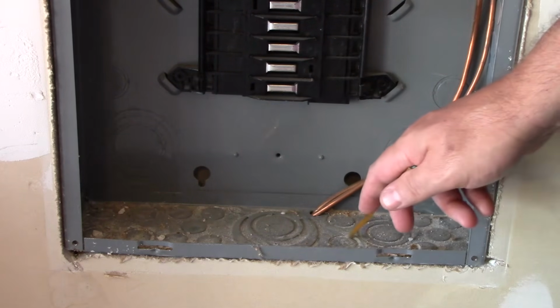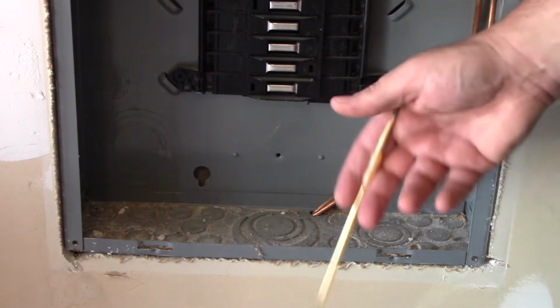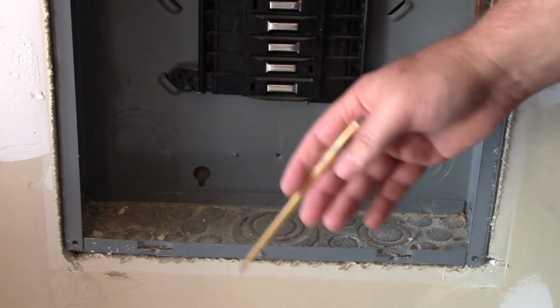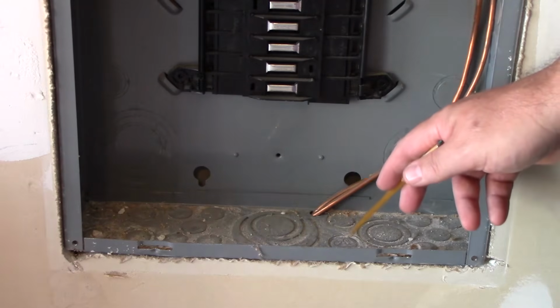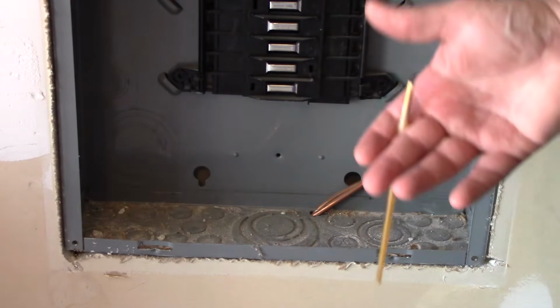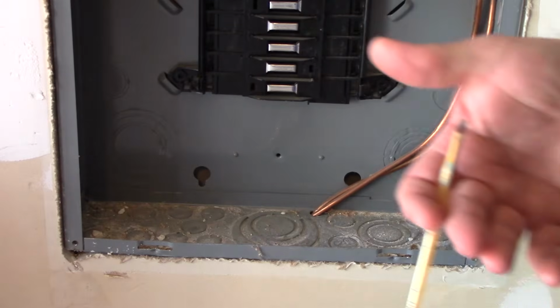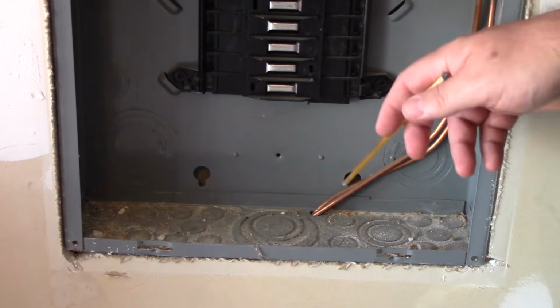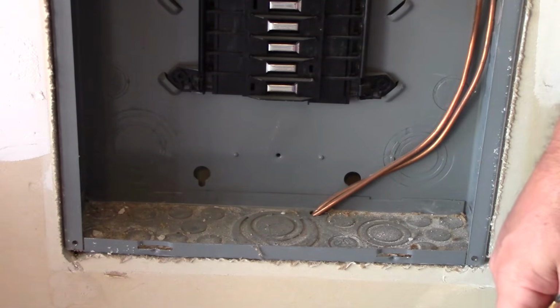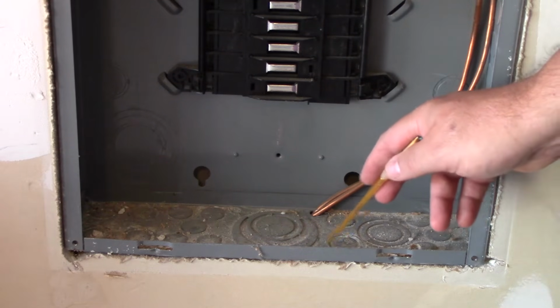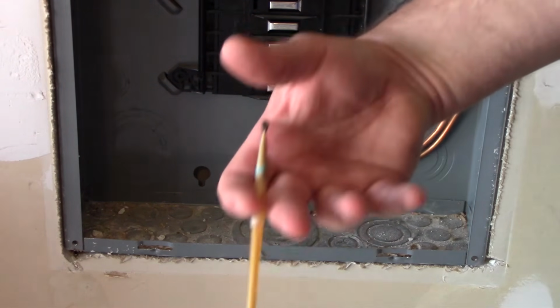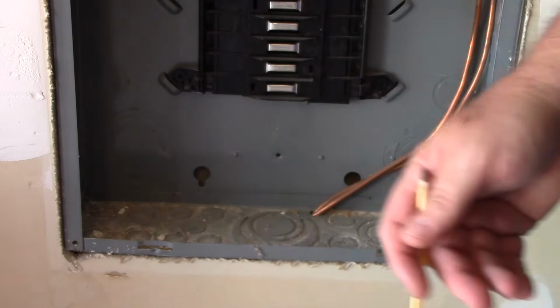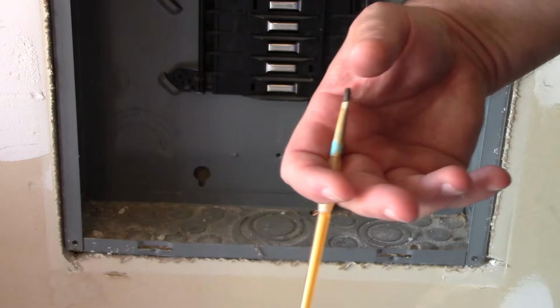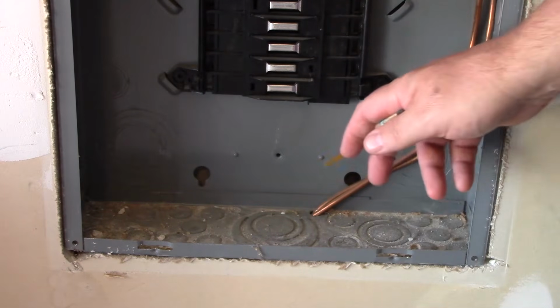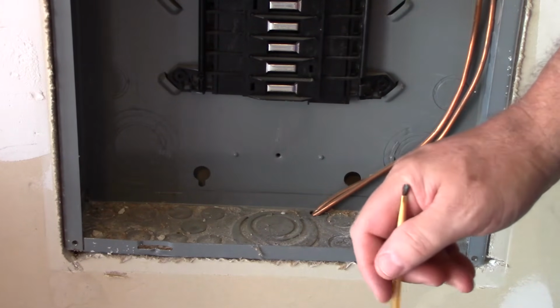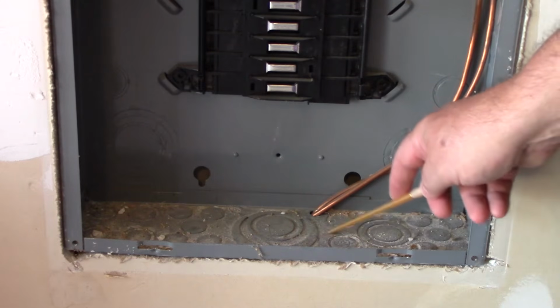Now, if they brought it through a knockout, let's say this is a 1/2 inch knockout, and they brought it in and didn't put a connector on it and it's just loose in there, then we want to call that out because it moves back and forth. Also, if it's ever used, maybe in a lightning strike application, where you're using this grounding electrode conductor, it could create an arc over here, and it could inhibit its use. It could create a choke effect, and what happens is it starts to decrease the effectiveness of that grounding electrode conductor. We don't even want to speculate on that, so we want it to be secured to this enclosure.